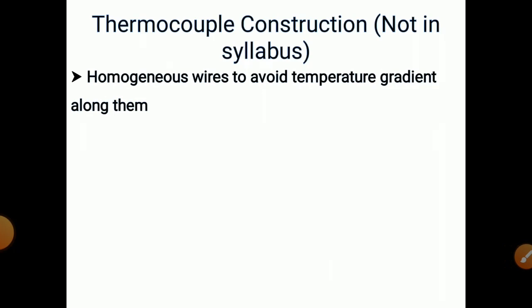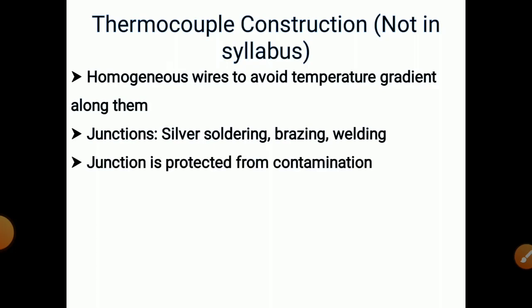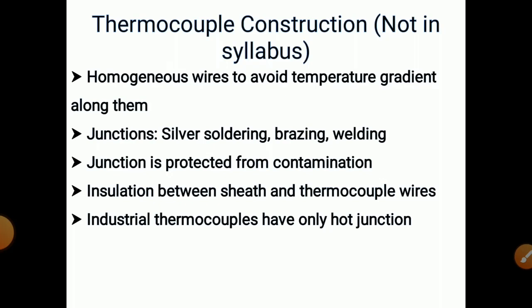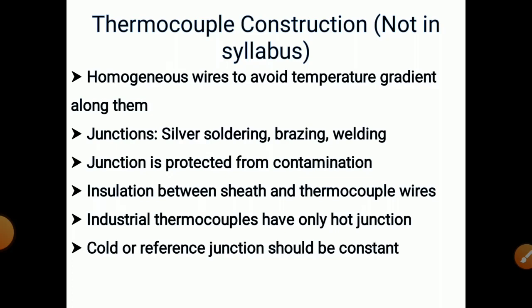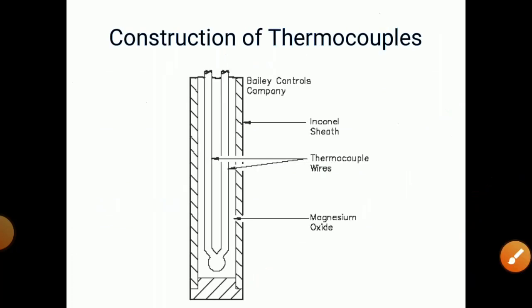For thermocouple construction, homogeneous wires are used to avoid temperature gradient along them. Junctions are provided with silver soldering, brazing, or welding. Junctions are protected from contamination, with insulation between the sheath and thermocouple wires. Industrial thermocouples have only one hot junction, and the cold or reference junction is kept constant. Insulation is provided to protect from contamination.